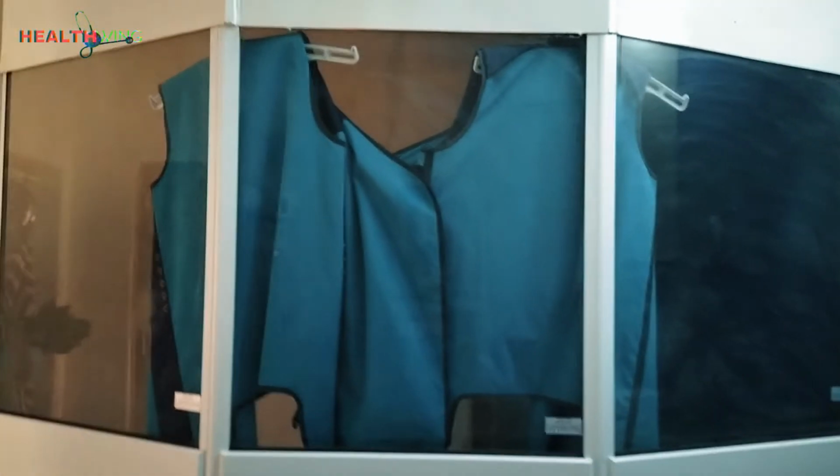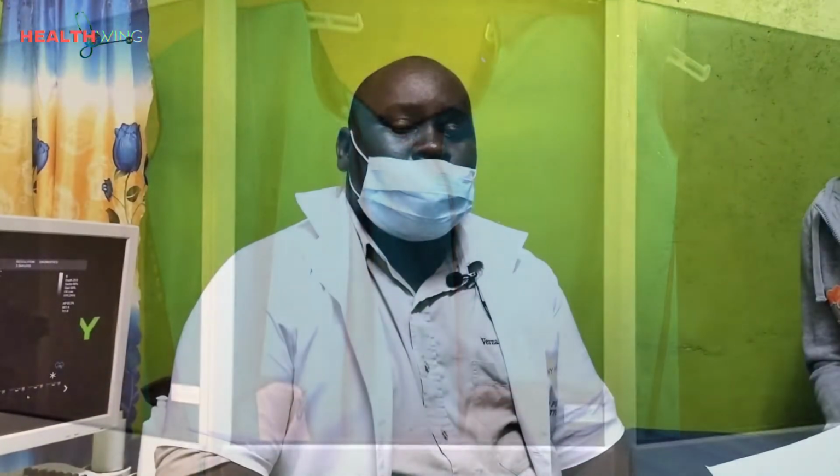That's one. Two, we try to reduce the amount of radiation by reducing the cases. For example, avoiding repeats, because the more you do it, the more the dosage accumulates inside the body. Another way of ensuring that we protect them is following the lead standards in any building during construction, so that we also protect the public. The radiation does not leak outside the radiation room. And we also don't have windows in any X-ray room. An ideal X-ray room does not have a window, so that there is no outflow of the radiation to the public also. So those are the few ones.